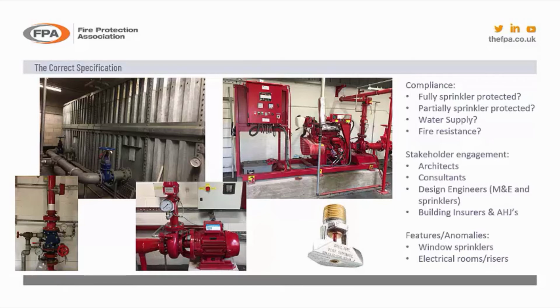They may be there because they've reduced the fire rating of the glazing. A fire from an adjacent building may need to be considered. So these window sprinklers have been added on, and the requirement for them is based on American standards, and they have to be fully hydraulically calculated. They have to be run for 90 minutes, depending on the spacing of the window mullions. The spacing of the sprinklers needs to be considered. And when you move them closer or further away, you increase the pressure requirement of the head, which increases the flow. And this flow for 90 minutes needs to be added on to your sprinkler system.